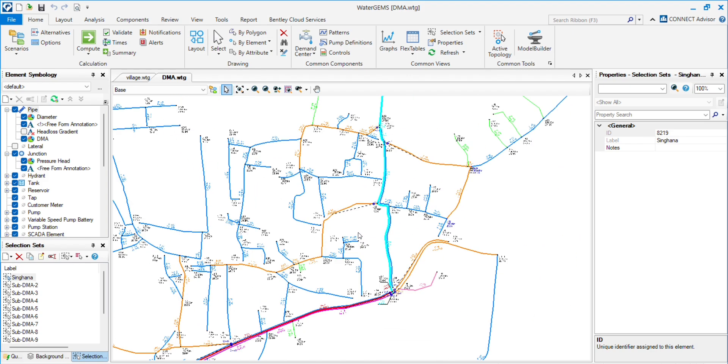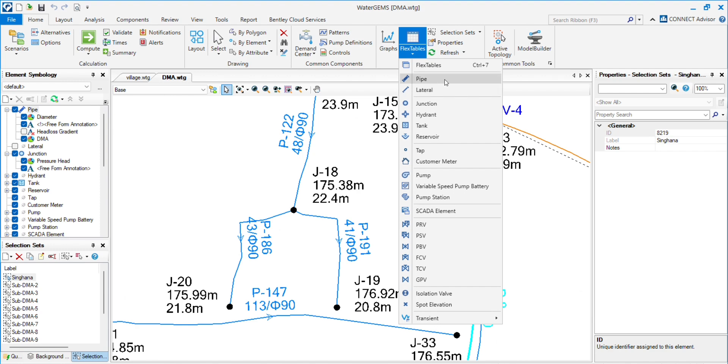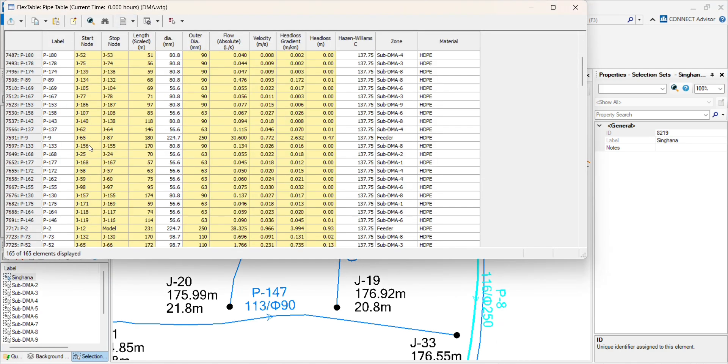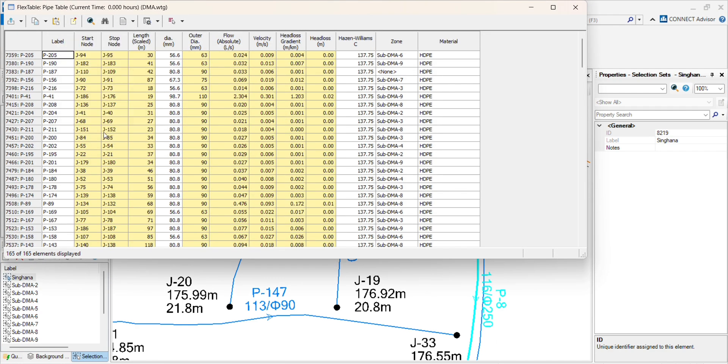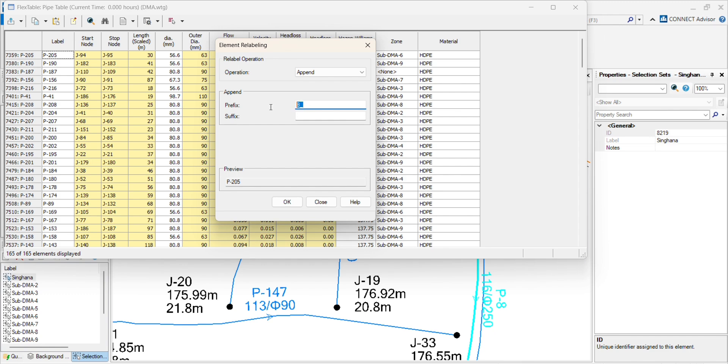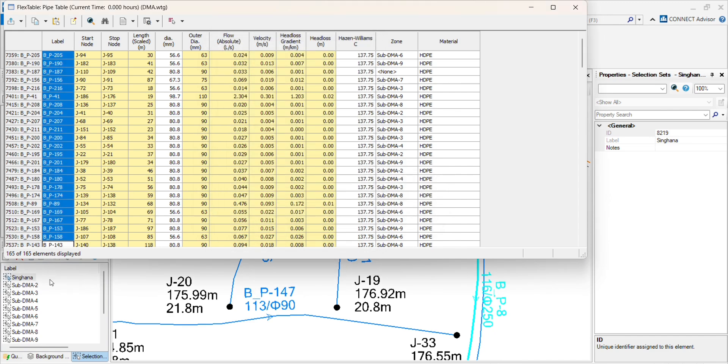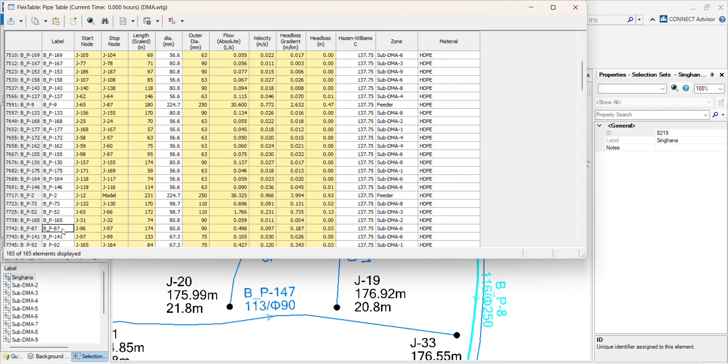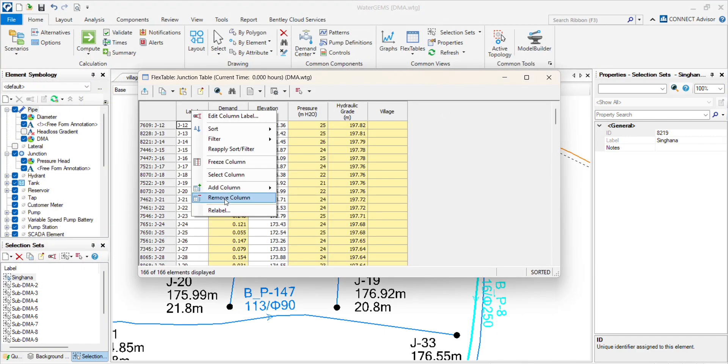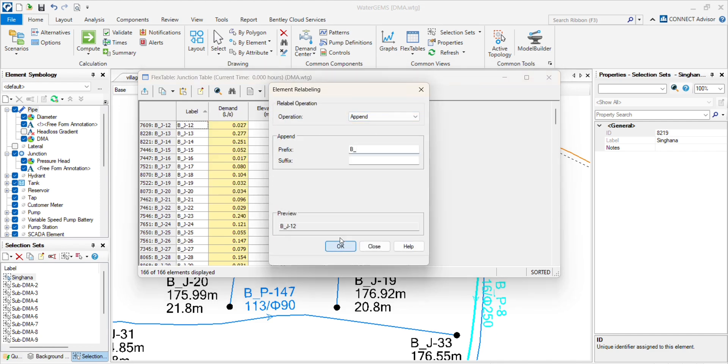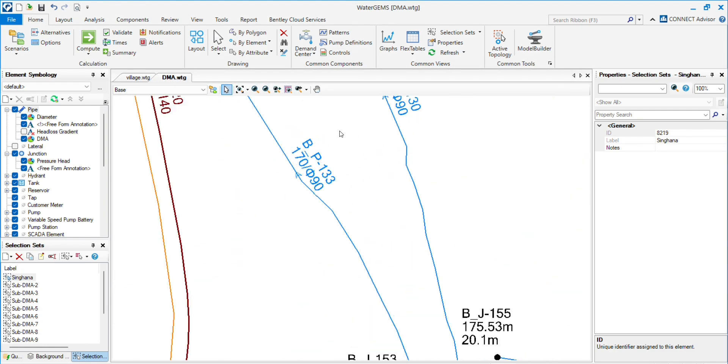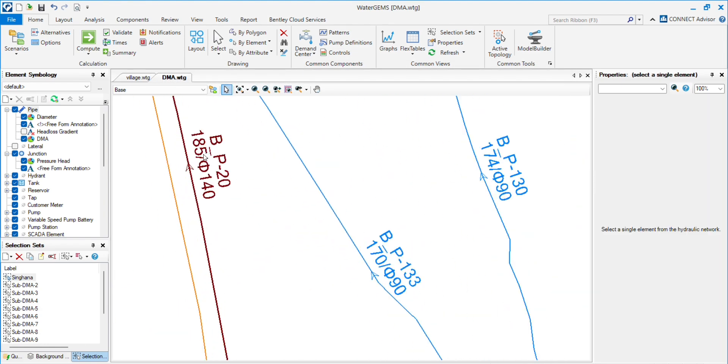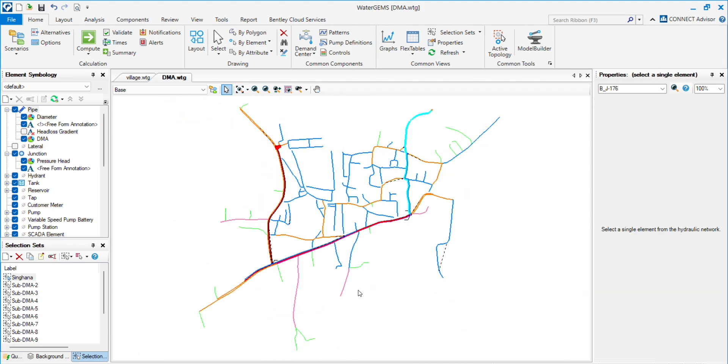We have this model. Now we will try to rename those elements. First we go to the pipe, relabel. Go to append. Append will give you prefix and suffix. I will click on prefix. And this is model B, so I choose prefix as B underscore. Click on OK. And you will see B underscore has been put in front of all the pipes. We have to do the same for the junctions. Click on junction, relabel, append. B underscore, OK. Now we will see pipes and junctions are relabeled, renamed.